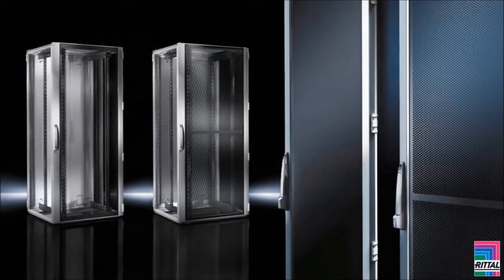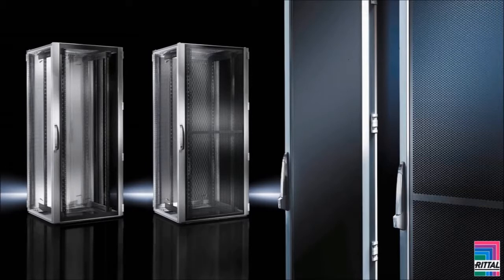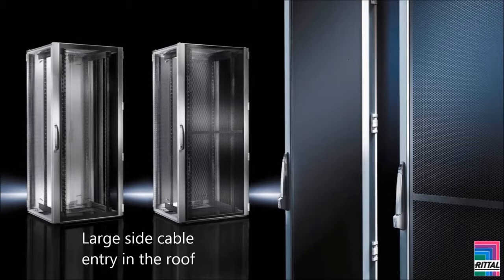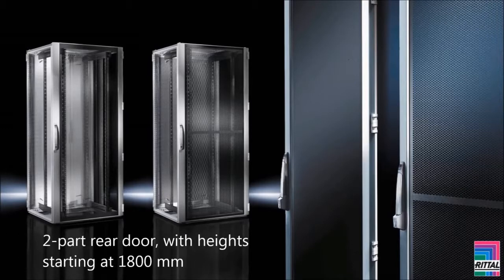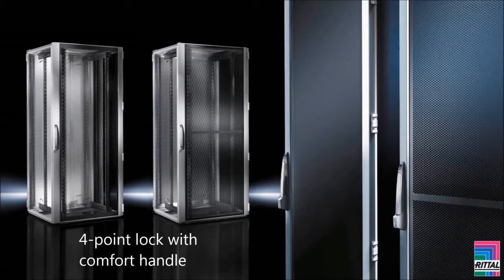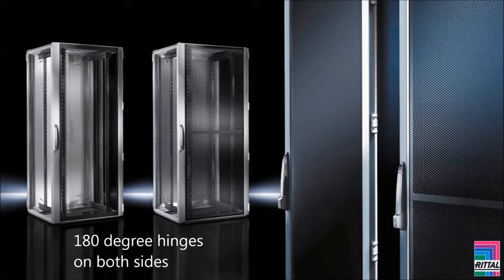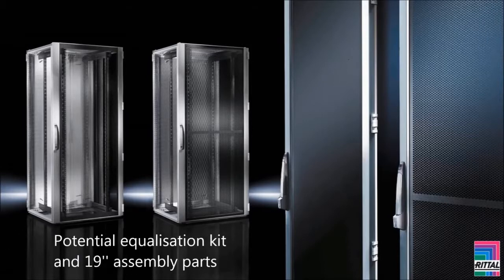Both variants include two 19-inch mounting levels up to 1500 kg, large side cable entry in the roof, two-part rear door with heights starting at 1800 mm, four-point lock with comfort handle for customized locks at the front and the rear, 180-degree hinges on both sides, potential equalization kit and 19-inch assembly parts.